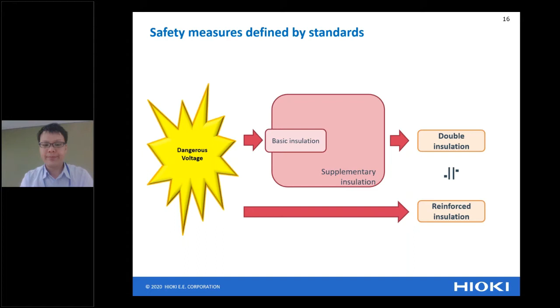This diagram shows class 2 equipment. For class 2 equipment, I said you need to apply two kinds of insulation. But if you can do reinforced insulation, it's okay. Basically, you need basic insulation and supplementary insulation. It means double insulation. This is better, but reinforced is also okay from the standard. That's all about the basics of electrical safety testing. It's just basic knowledge.